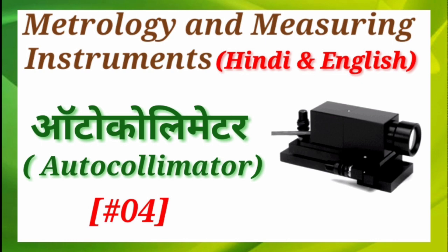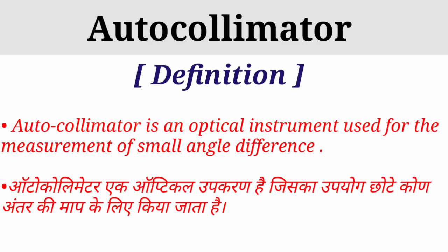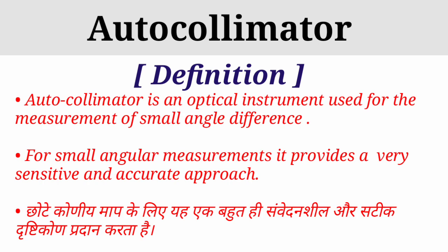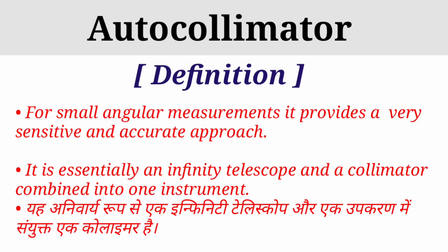So let's start. First of all, the definition: an autocollimator is an optical instrument used for measurement of small angle differences. It means an autocollimator is an optical tool for small angle measurement. It provides a very sensitive and accurate approach. It is essentially an infinity telescope and a collimator combined into one instrument.